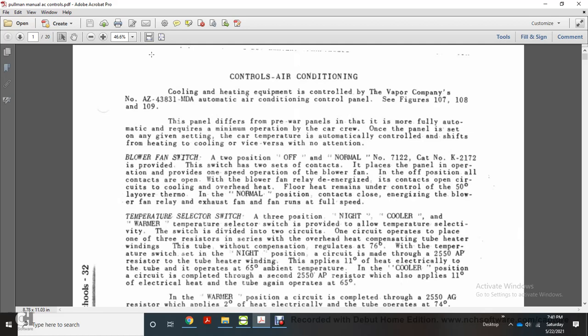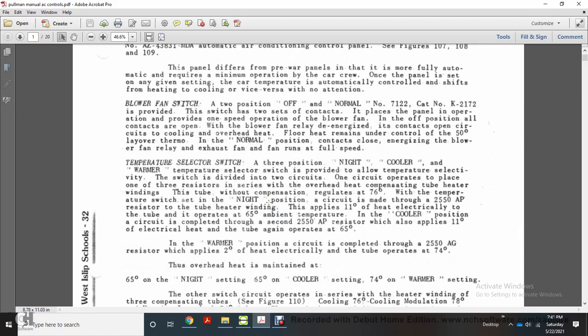The blower fan switch, catalog number K2172, is provided with two sets of contacts. In the off position, all contacts are open; the blower fan relay de-energizes, opening circuits to cooling, overhead heat, and floor heat. Floor heat remains under control of the 50-degree layover thermostat. In the normal position, contact closing energizes the blower fan relay and the exhaust fan runs at full speed. The temperature selector switch is a three-position switch — night, cooler, and warmer — providing all temperature selections divided into two circuits.